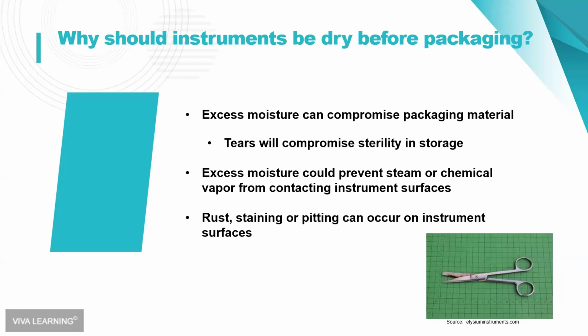The other reason we dry instruments is that excess moisture on the instruments could actually prevent the steam or chemical vapor from contacting instruments while they're in the sterilizer. Just like blood or cement or other debris, excess moisture can be a barrier as well. And finally, if you don't dry your instruments well, before you put them in the packaging and in the sterilizer, you can get rust, you can get some staining or pitting on your instrument surfaces.